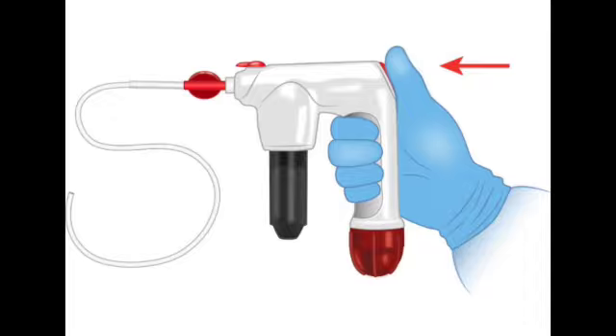So what happens when you press it? When you press the trigger for the first time, you do not get a massive blast of powder. You usually only get a very small, anemic puff. Because the powder is still traveling from the handle. Right. Fighting all that dead air all the way down the length of the catheter. The system requires priming. Exactly. The established technique is to press the trigger for a couple of seconds, just to get the powder moving through the lumen of the tube. Then you release and quickly press it again. That consecutive rapid second press is what finally unleashes the payload.